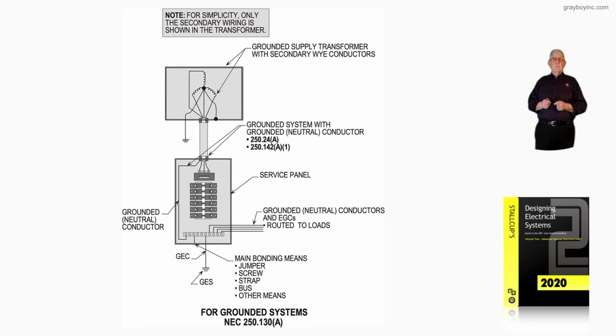Now this illustration deals with grounded systems. And basically, this is in accordance with 250.130A. But now reviewing the transformer, notice that the Y-connected secondary is connected to ground, the XO is. And then note 1 says we're just showing the secondary wiring, basically.